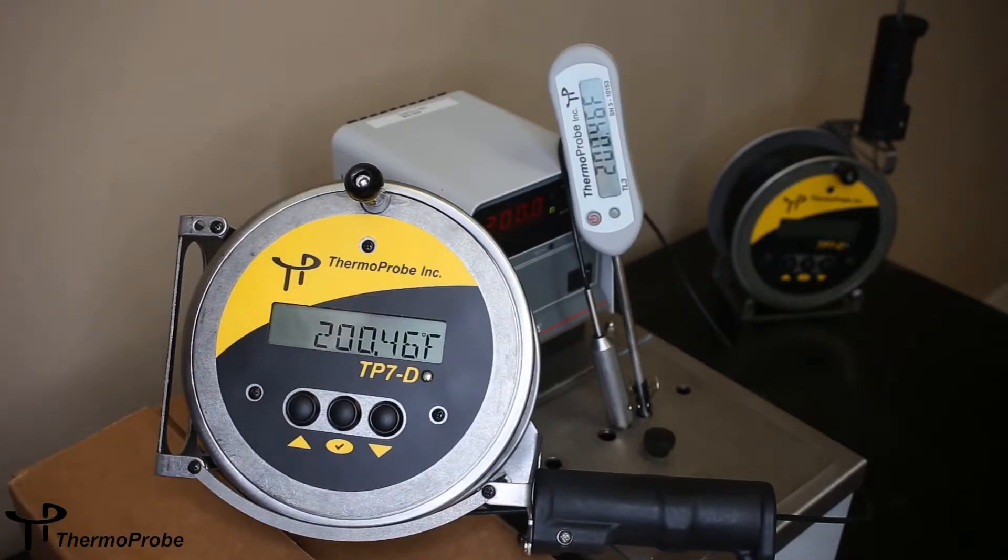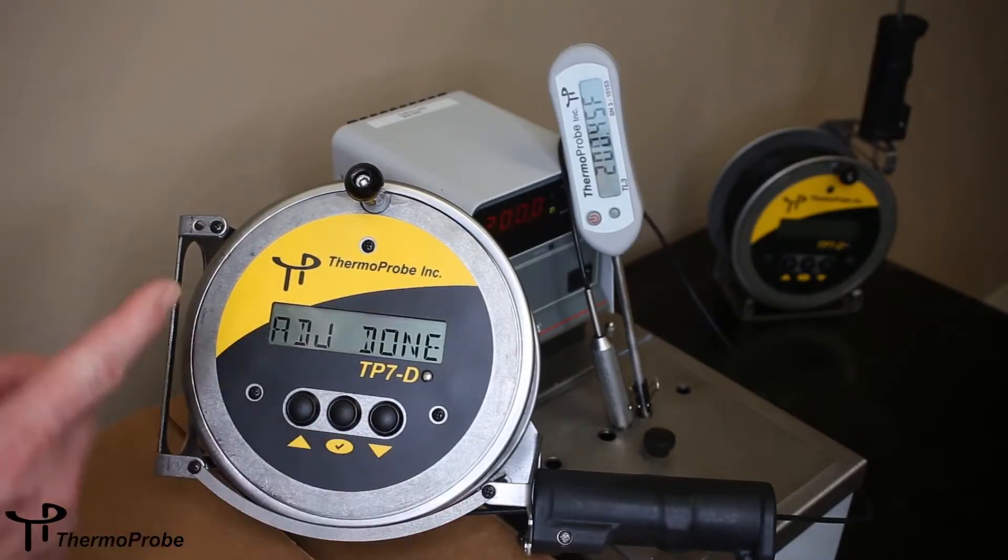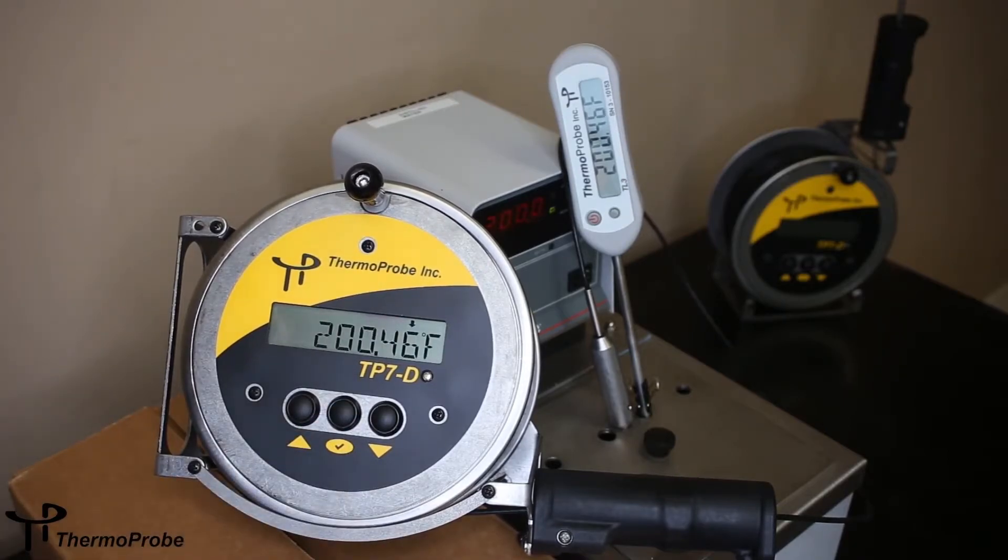All right. Once we're happy that those two match, we hit select. We get a save. We confirm that by selecting again, and it says adjustment done. We want to hit select on that, and we've completed our calibration.